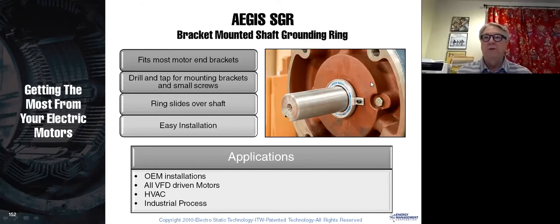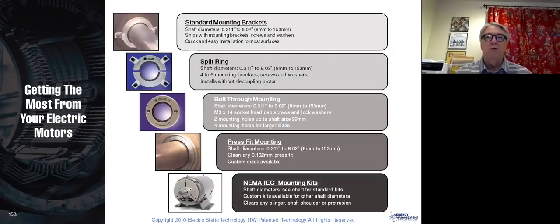So you still get the currents, but the currents, instead of going through the bearings, go through this grounding ring, and that prevents the voltage from getting high enough so that it can arc through the bearing. Do these work? Well, I was kind of skeptical when they first came out. I can assure you they work. And we have had very good luck with them. We put shaft grounding rings on lots of motors these days.